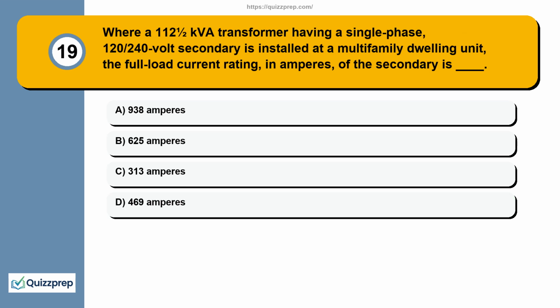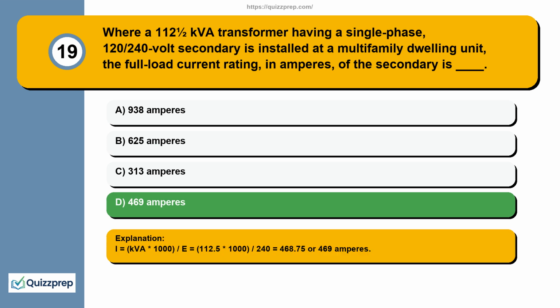Question 19. Where a 112.5 kVA transformer having a single-phase, 120/240 volt secondary is installed at a multifamily dwelling unit, the full load current rating, in amperes, of the secondary is: 938 amperes, 625 amperes, 313 amperes, 469 amperes. I equals kVA times 1000 divided by E, equals 112.5 times 1000 divided by 240, equals 468.75, or 469 amperes.